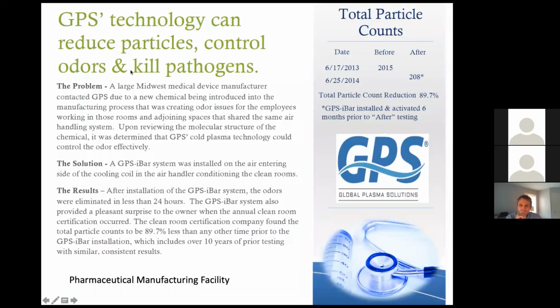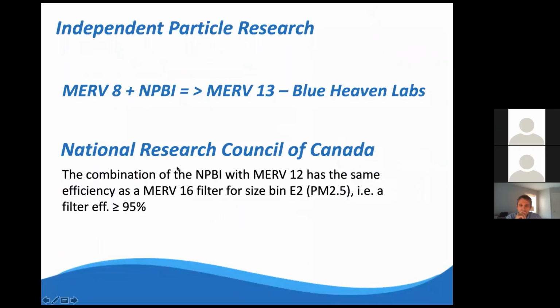Now, with our technology, when you ionize the air in the space, even in a clean room environment, so pharmaceutical applications like this can see a huge reduction of particles. Here we have a clean room manufacturer, this was actually catheters being manufactured in this clean room, and they saw almost a 90% reduction in total particle counts, even in a clean room environment with a very high air exchange rate using HEPA filters that were 99.99% efficient. And so we can impact those ultrafine particles. We also have a lot of independent testing that shows taking an existing filter and simply adding our technology into the system will make the filter more efficient. So right now, ASHRAE is recommending through their COVID-19 task force to increase your MERV ratings up to a MERV 13, which is not a bad idea.